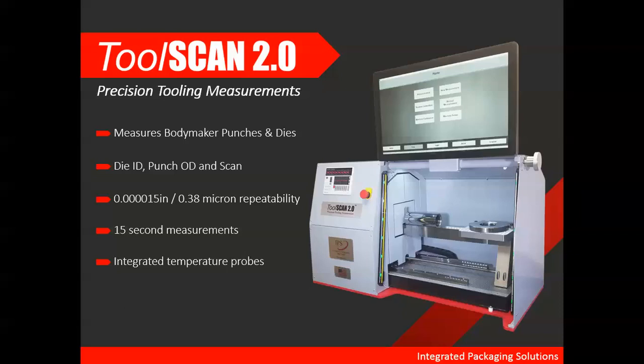There are also integrated temperature probes, and these do two things. First, they match the temperature at which the machine has been calibrated. Calibration is done at a given temperature, so if a measurement is about to be performed and the current temperature differs significantly from the calibration temperature, a big red flag appears saying it's time to calibrate again.